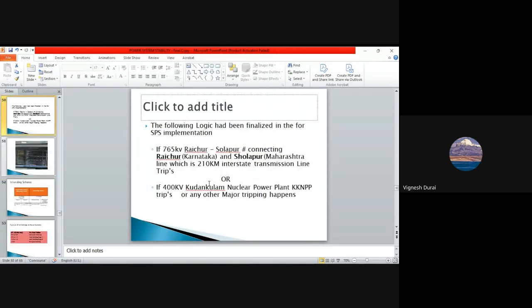Okay. This special protection scheme, the following logic has been finalized in the special protection, SPS is special protection scheme. For example, I have taken a line. It is a 765 kV line from Raichur to Solapur. It is an interstate feeder, where Raichur is in Karnataka and Solapur is in Maharashtra. It is 210 kilometers. Here you have more than 1000 megawatt transmission between these lines.